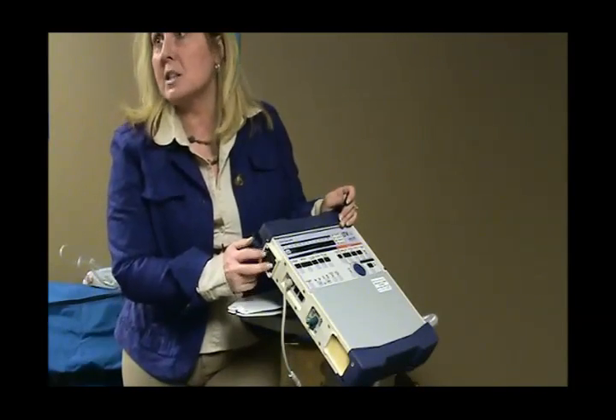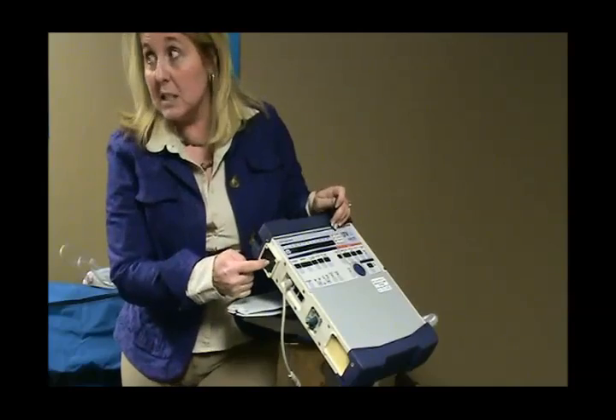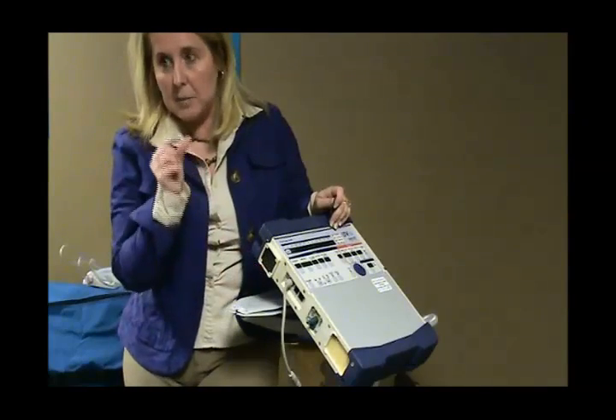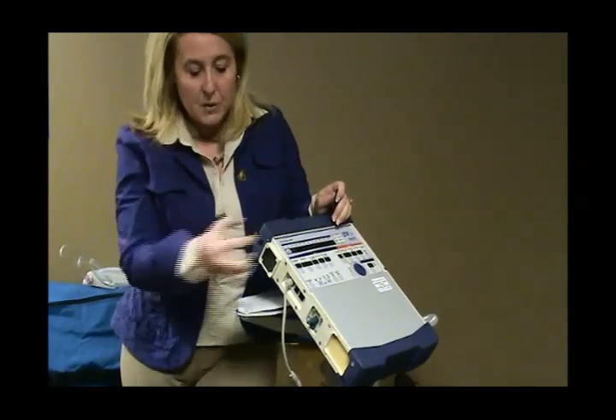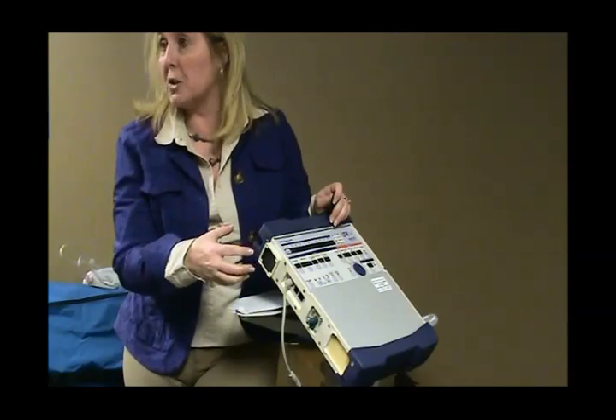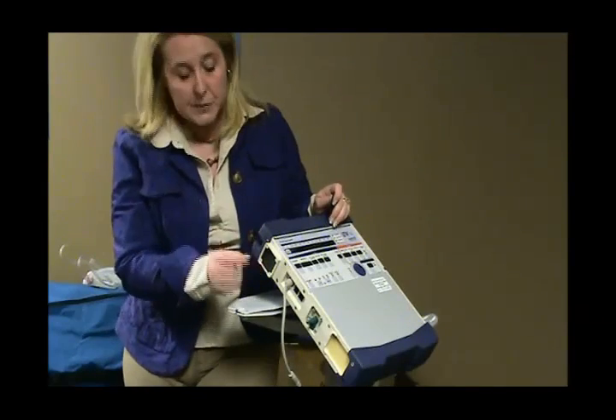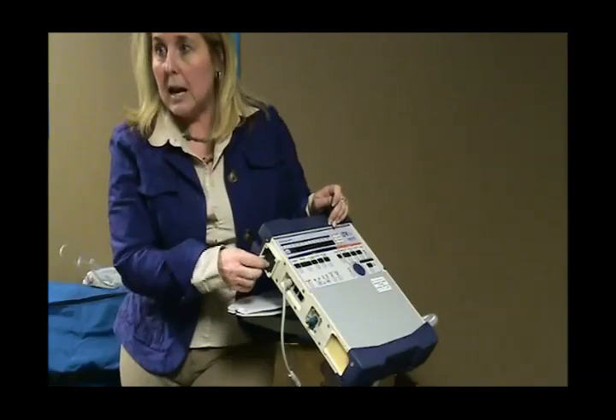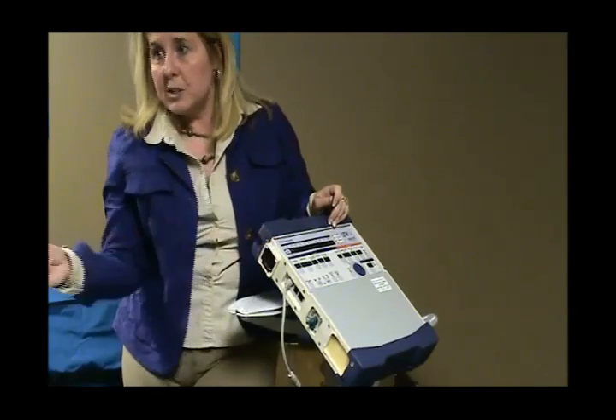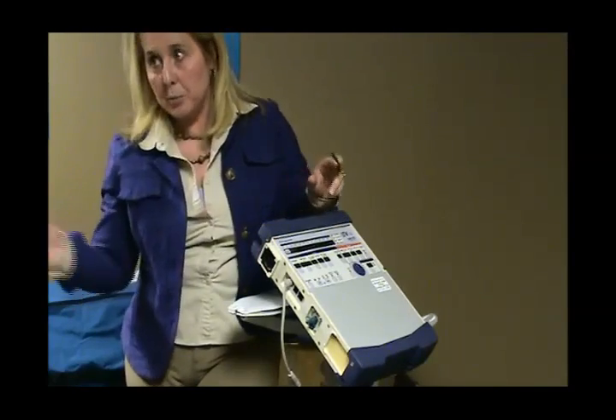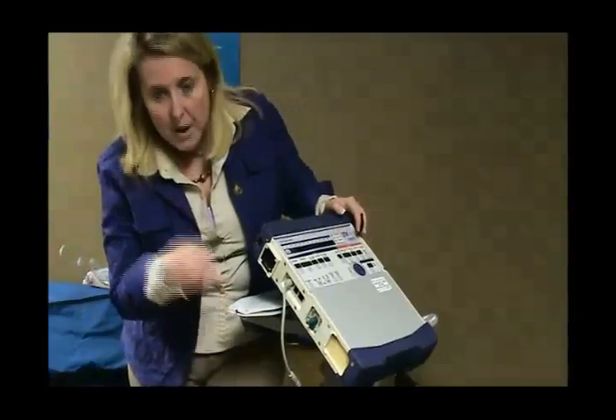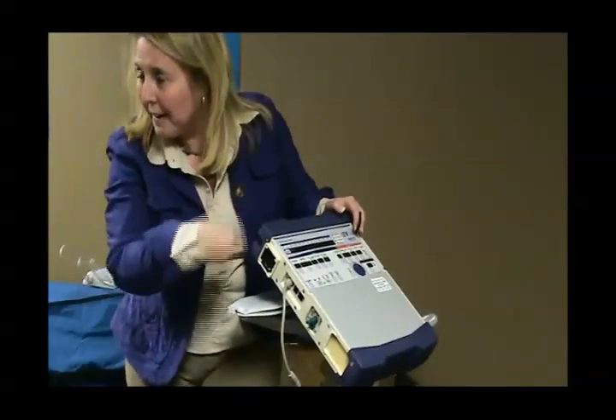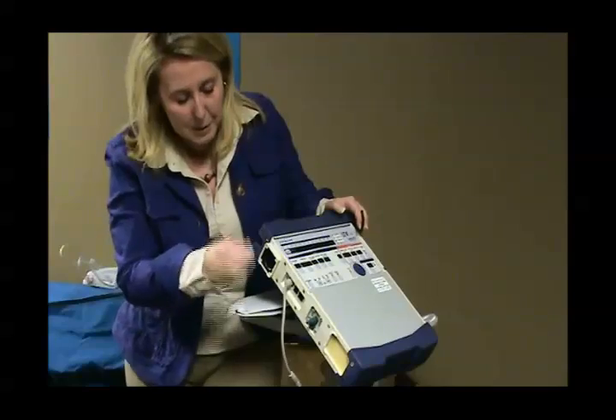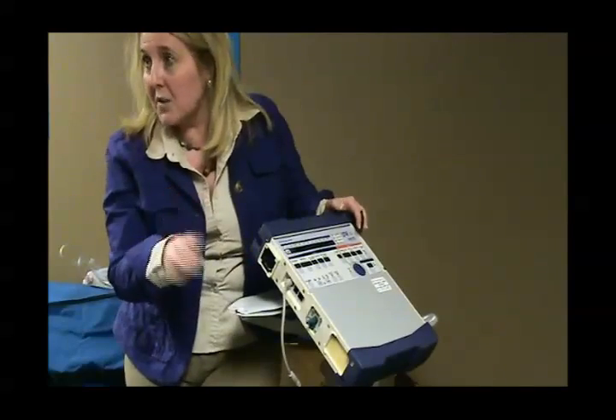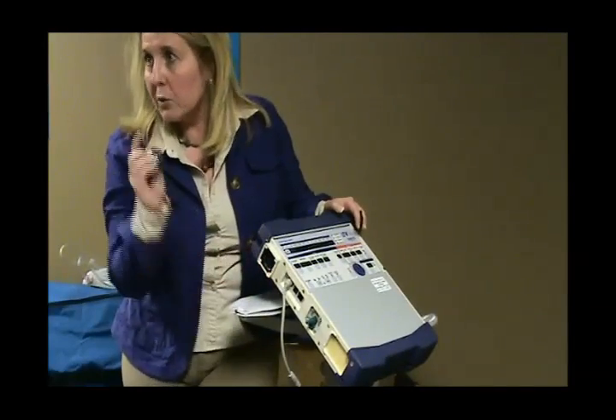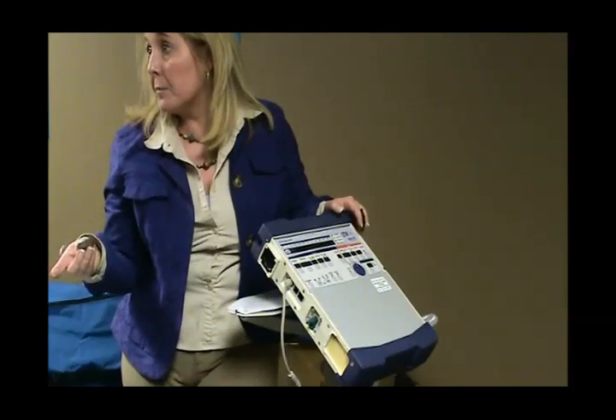The other thing that can cause that HW fault is if nobody cleans this thing for a really long time and it gets this much dust on it, and the ventilator can't get air in to cool the electronics, it'll give you a hardware fault. I've seen them before, they were just coated. Had a hardware fault, took this off, cleaned it, actually threw that one away because it was so nasty. I actually took an oxygen tubing and blew in there. Ventilator wasn't running on anybody, by the way. Blew it in there to get the dust off of it and put a new filter in there, reset the ventilator, and it started back up, okay?